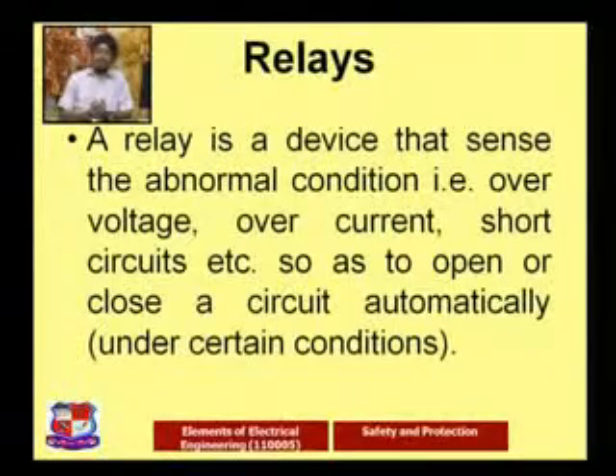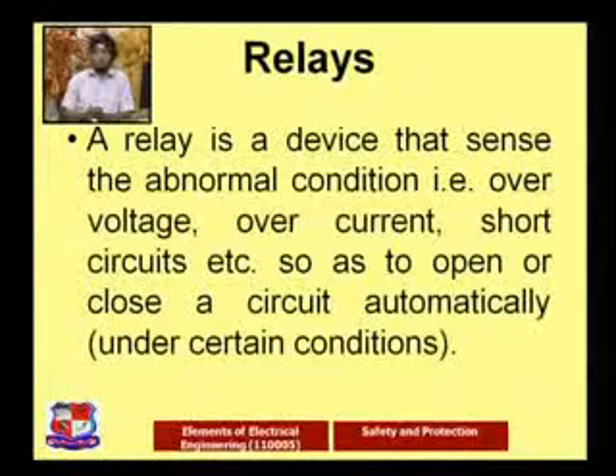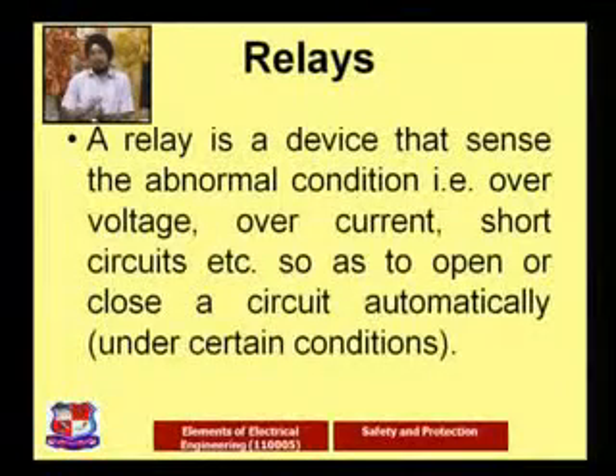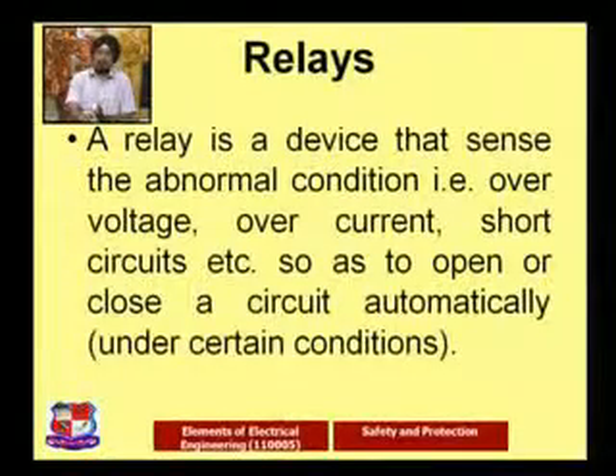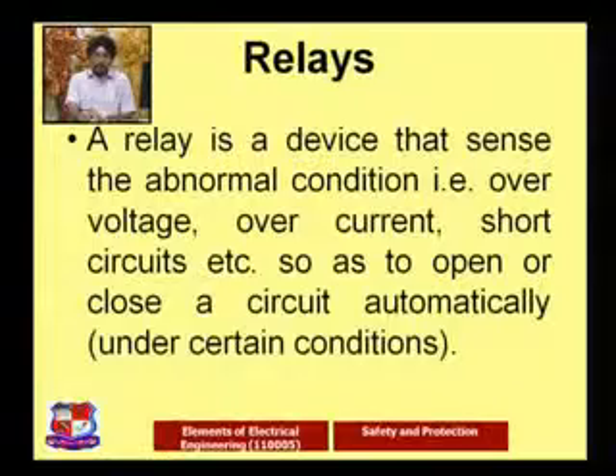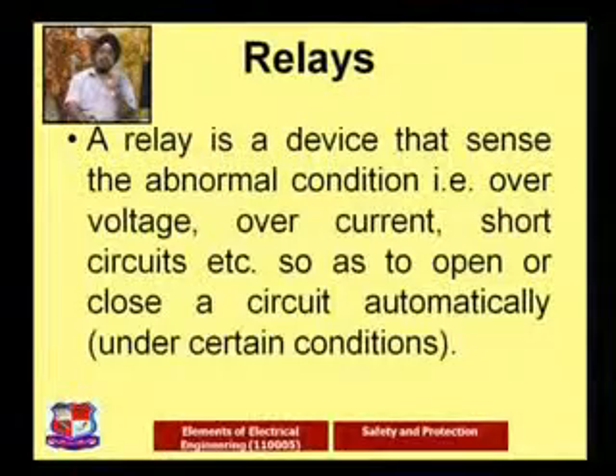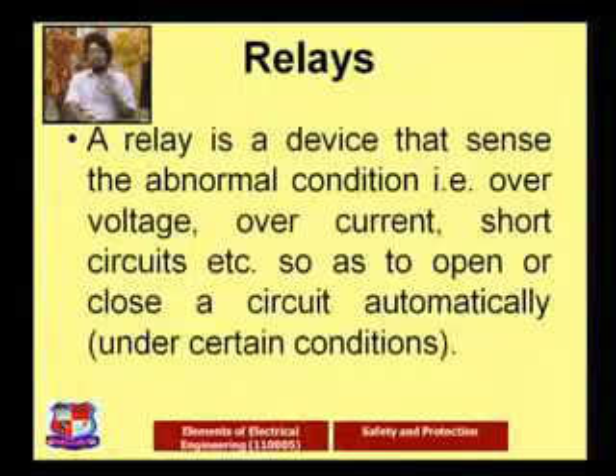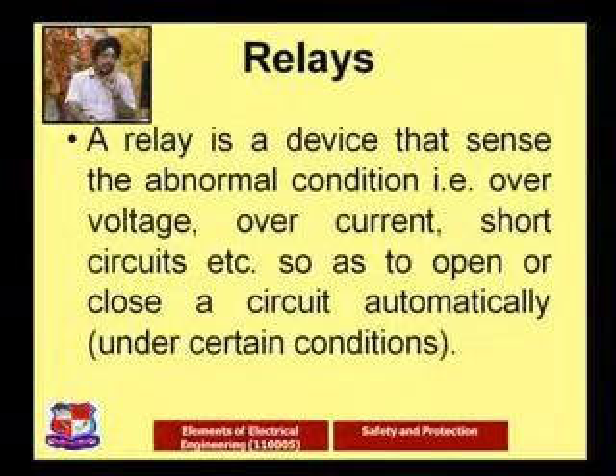It may happen that the relay senses the fault, but for a few microseconds the fault clears, so it can open and then close again. So the circuit may trip or may not trip, but what is important is that the relay senses that some abnormal condition is there. If the fault clears after some time, it's fine. If it does not clear, the tripping signal will pass to the protective device in that particular case.